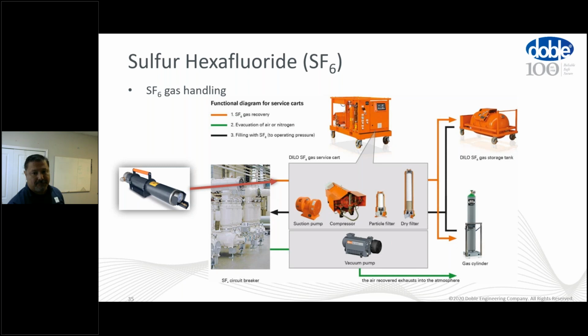The 3 R's. For vacuum, obviously you don't do that with pressure. The vacuum pump is going to be the only component that generally has oil with it. Obviously oil and SF6 do not do very well together. So the vacuum pump is strictly designed to evacuate air and moisture from a compartment. You would also use it, of course, to evacuate air and moisture from cylinders or a storage tank in this application.